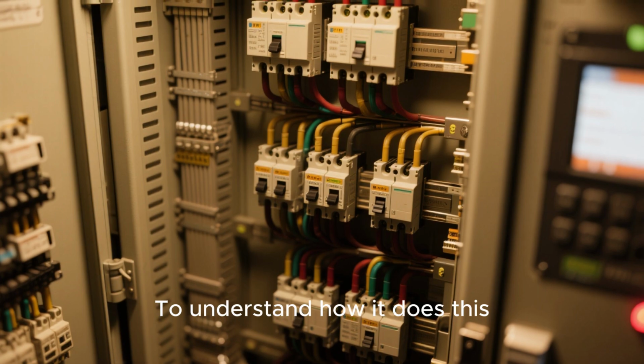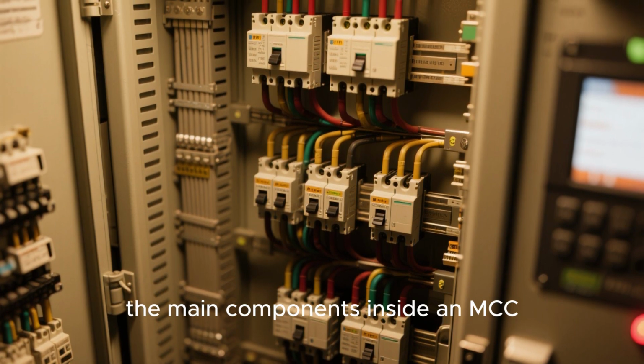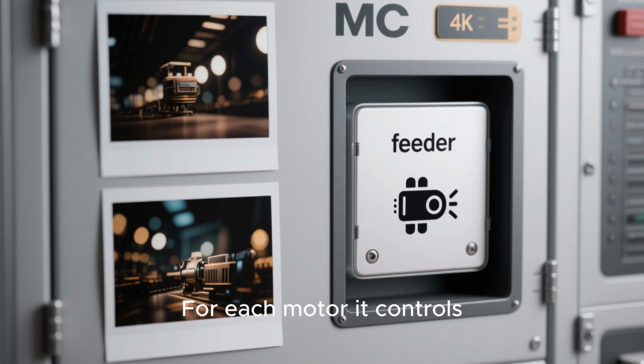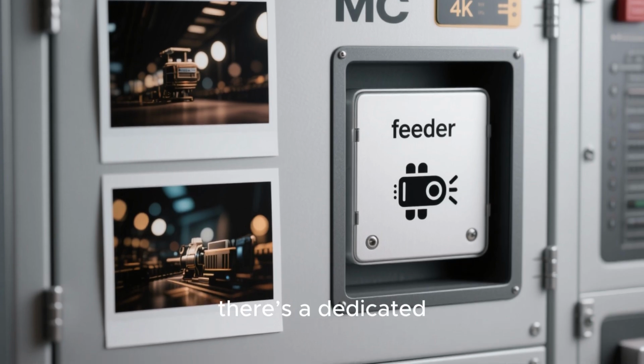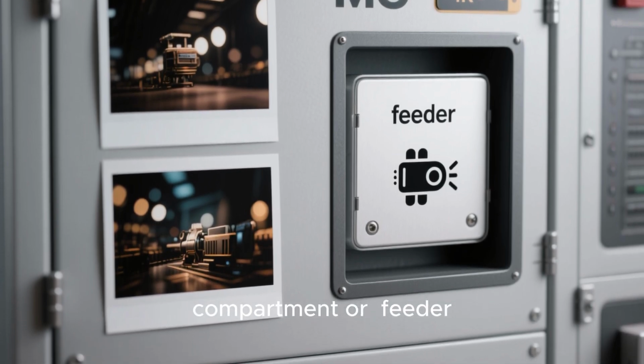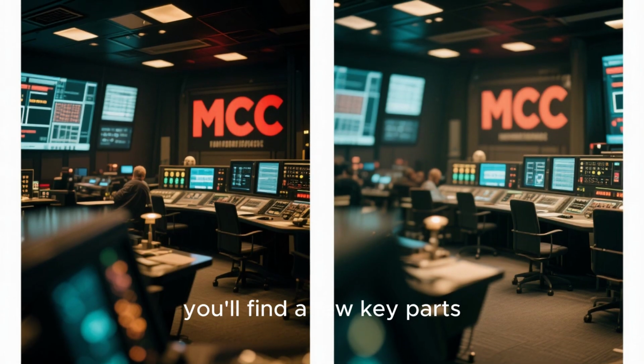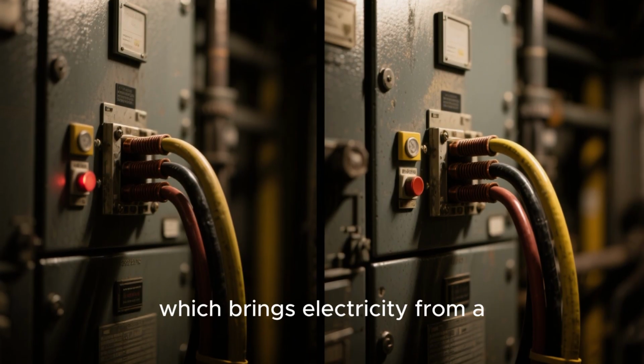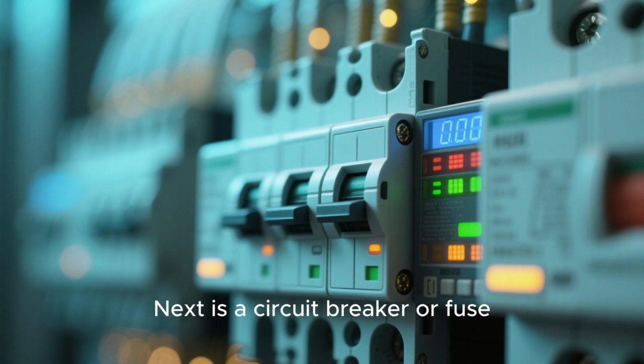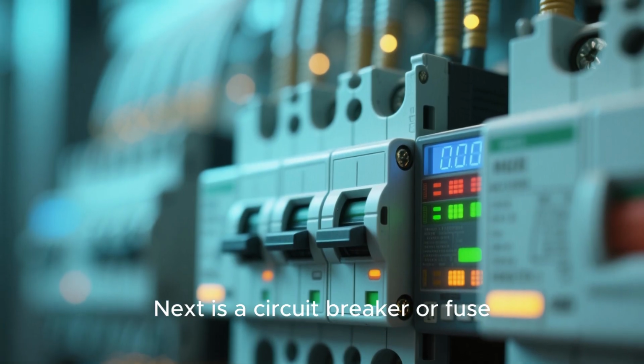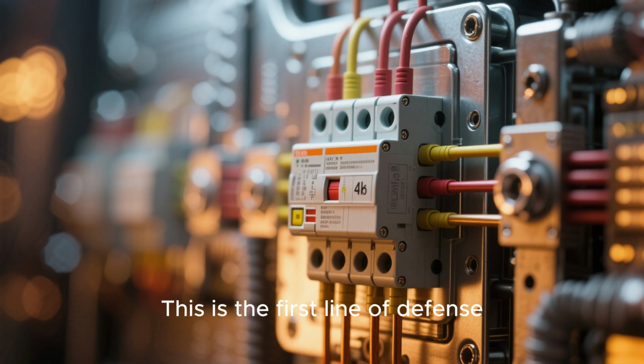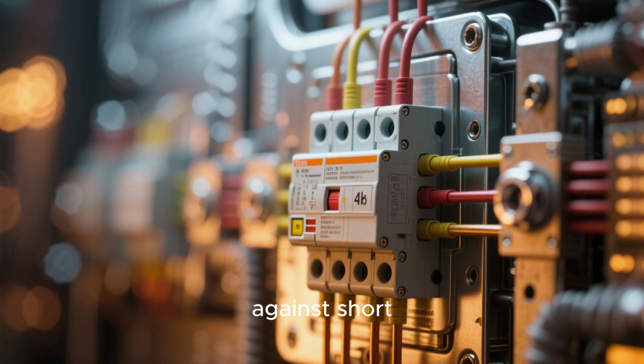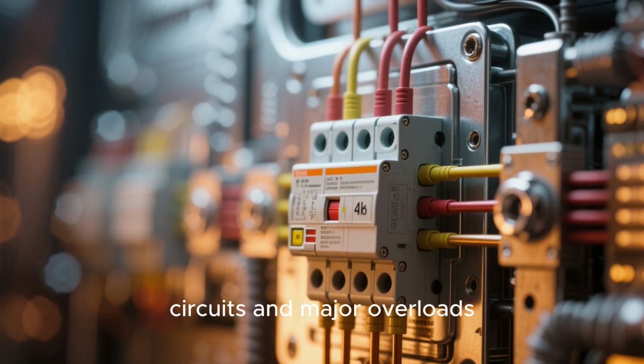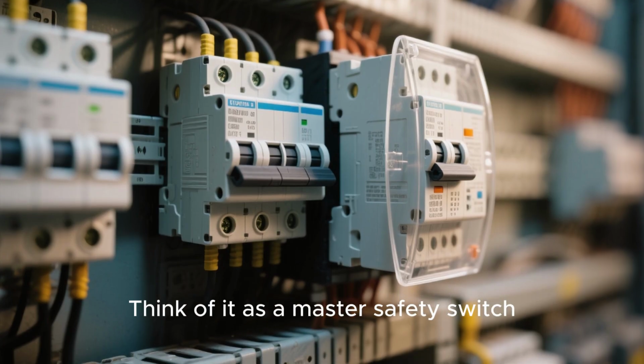To understand how it does this, let's look at the main components inside an MCC. For each motor it controls, there's a dedicated compartment or feeder. Inside this feeder, you'll find a few key parts. First, you have the incoming power supply, which brings electricity from a transformer or main distribution panel. Next is a circuit breaker or fuse. This is the first line of defense, protecting the circuit against short circuits and major overloads. Think of it as a master safety switch.